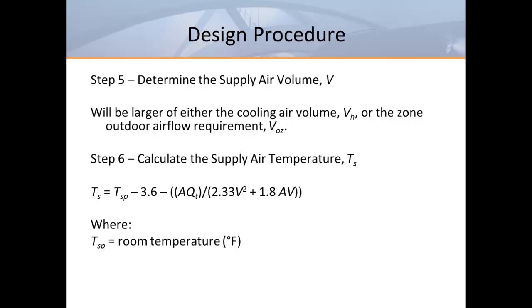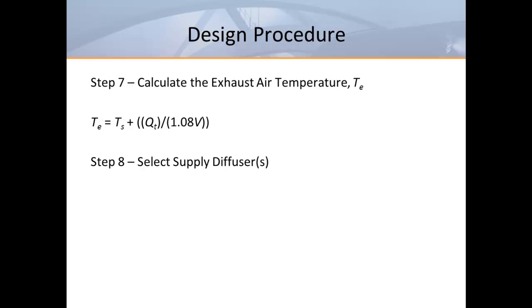Next we can calculate the supply air temperature needed to meet our room temperature set point. Once we know our supply air temperature, we can easily calculate our exhaust air temperature. Now it's time to make our diffuser selections. I went through this design procedure mainly to reinforce and apply the theory covered earlier. Most engineers don't have the time to go through an exercise like this, which is why most manufacturers offer product selection software to simplify the process and save valuable time.